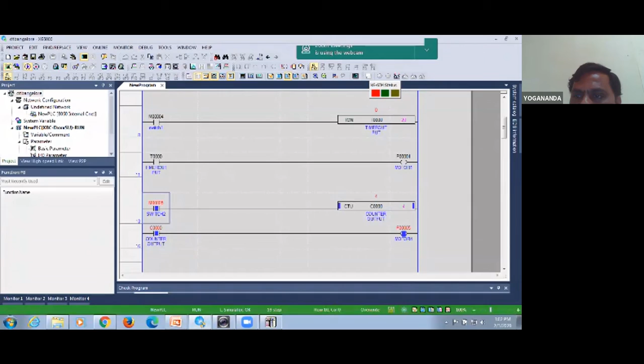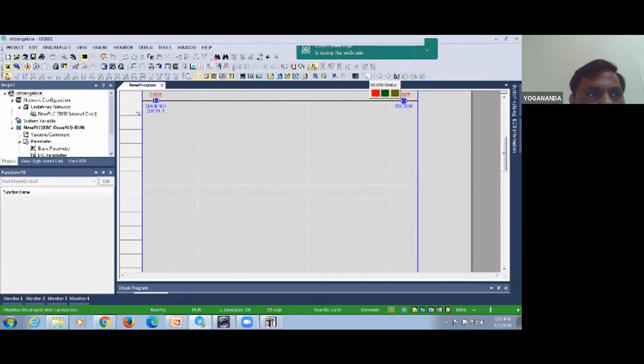I'll read out here. Our intention is to start the pump by observing the start switch condition, liquid level switch condition, and reservoir condition. Normally, you can use this application in homes to stop the motor when your tank is full, or start the motor when the water level in the tank is below the reference line. For this, we need 3 switches: the start switch, one more liquid level sensor or liquid level switch, and the reservoir switch. The output is the pump. 3 input switches and 1 output. I'll show you how to create the ladder diagram for this application. Stop simulation.